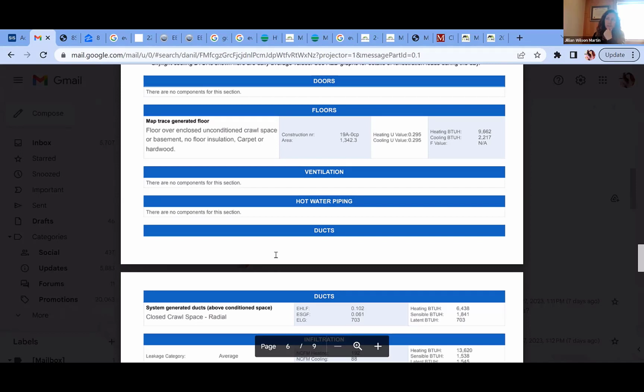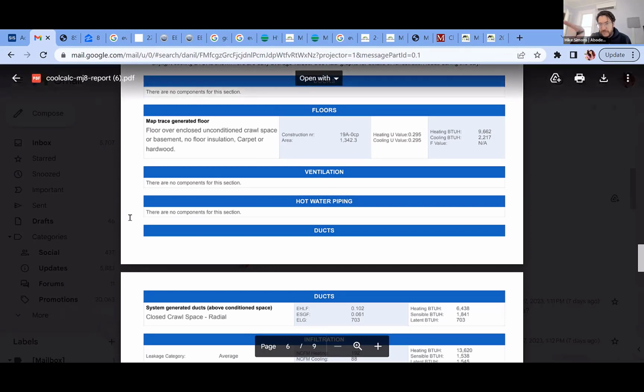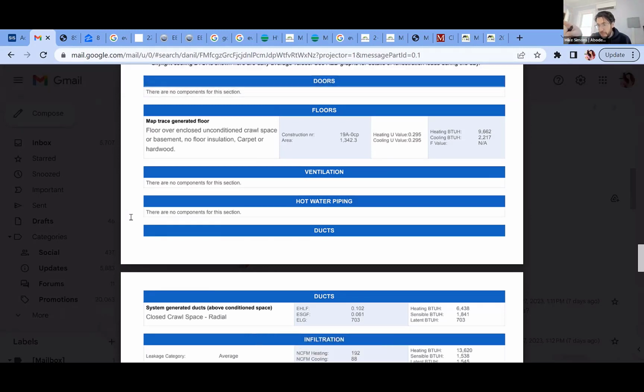Yeah, okay. So one thing to know is with Mass Save, if you do switch to whole home heat pumps, you can get Mass Save to insulate the basement ceiling, which is something I'd recommend doing to potentially bring down the heat load. Because once you're not running your boiler, there's going to be a lot less jacket losses, cycling losses, and pipes radiating out, so it will be cooler down there. I'd recommend insulating the ceiling to slow down the conductive and radiant heat transfer from your first floor down into your basement.